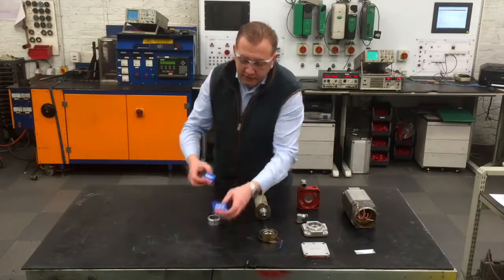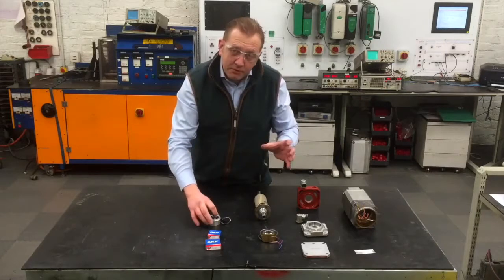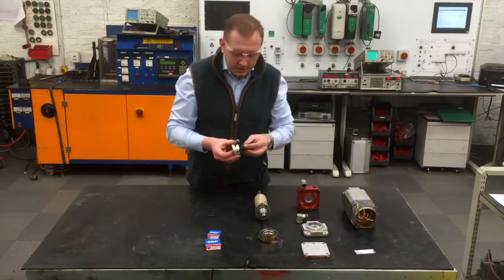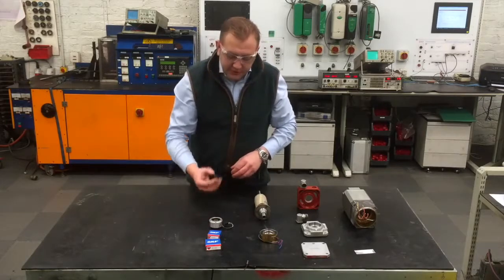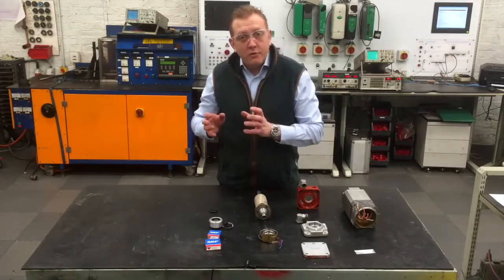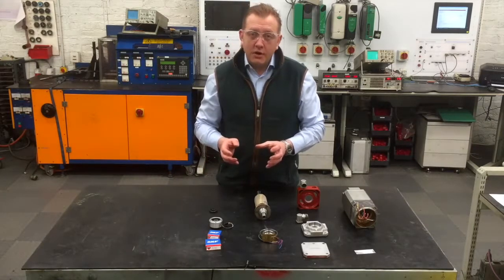What we will do now is fit two new bearings to the rotor. We will assemble the motor, we have got a new resolver here which will fit and align. We will then fit the all important shaft seal, assemble the motor complete, and perform a light test first of all before we perform a full load test on our load test rig.